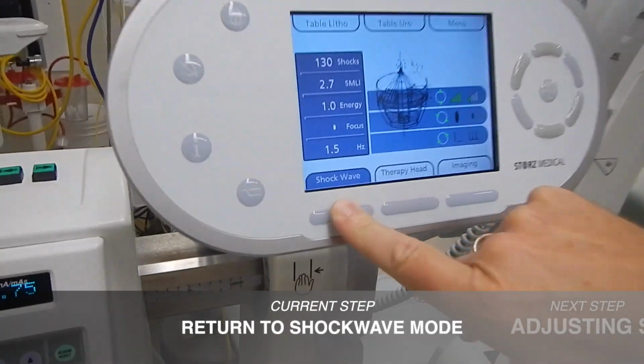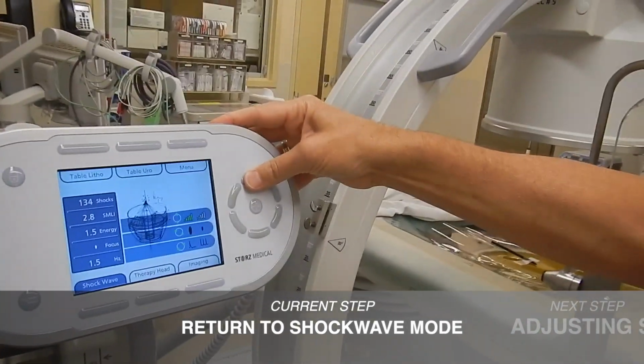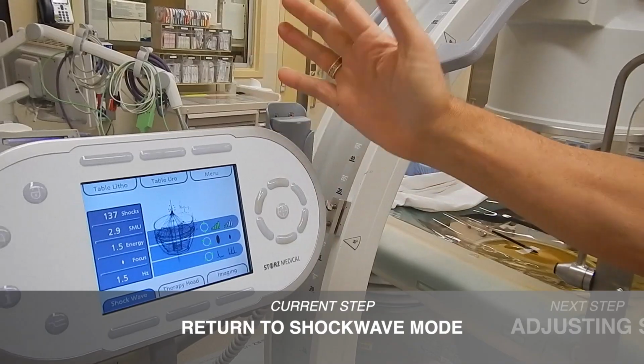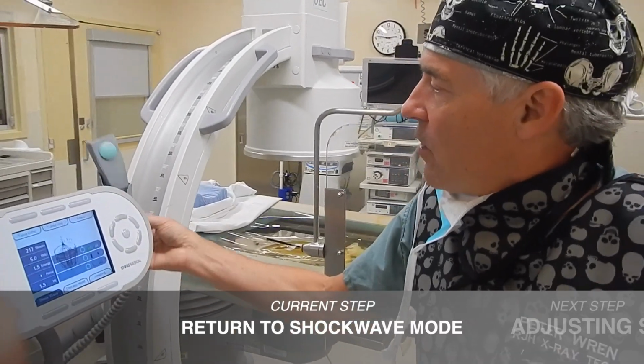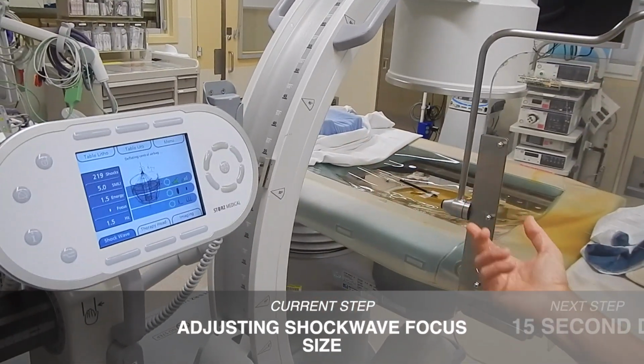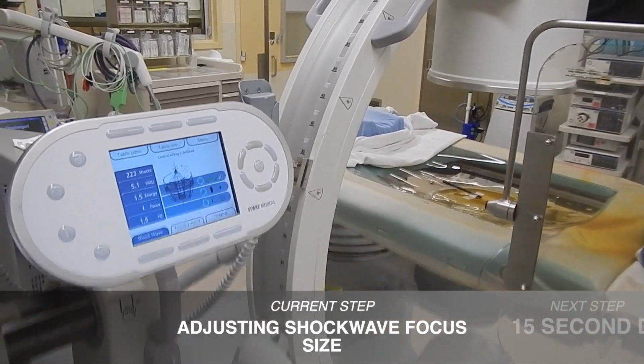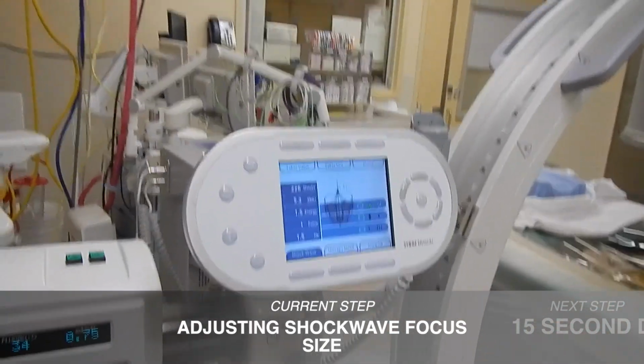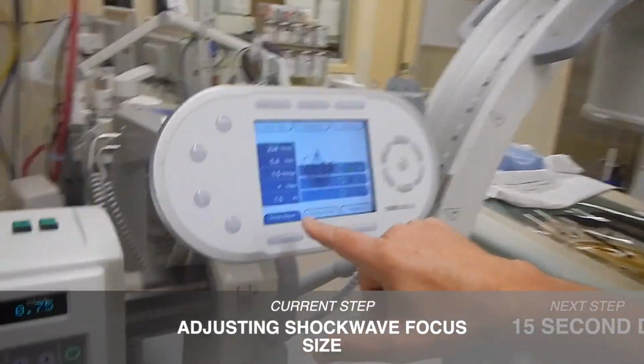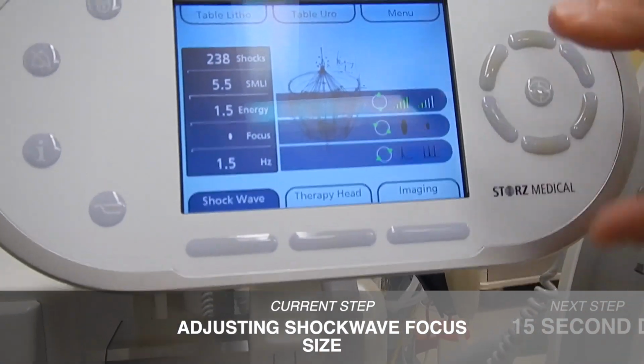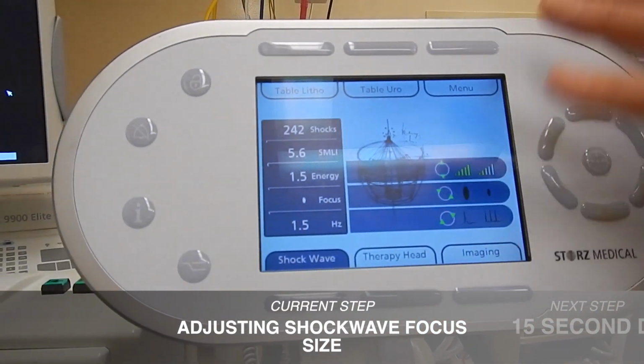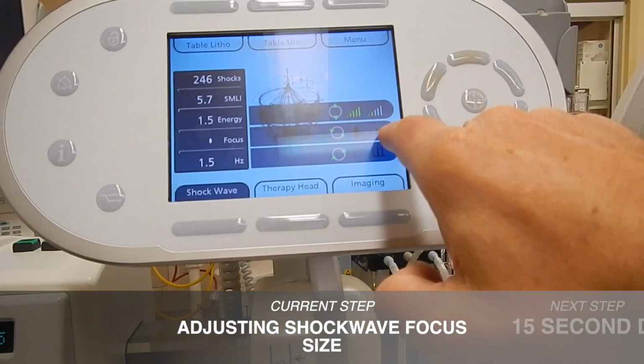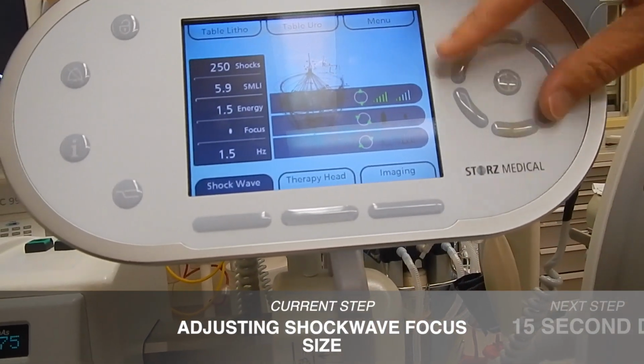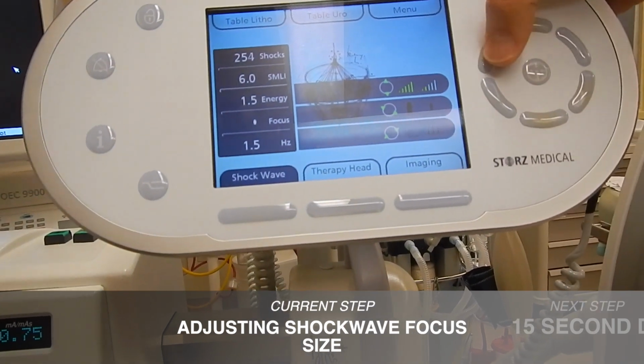Once they're happy, you let go, and you always put it back to shockwave, because the urologist may want to raise the energy, lower it, whatever. Okay, so when the shock waves are being applied, a certain amount will have already been applied, and the urologist may want to increase the focal size, so that's easy to do. If it's in shockwave mode, these buttons now coordinate with different aspects of the shockwave mode. So for the focal size, it's these two buttons. So to increase to large, you press this one.